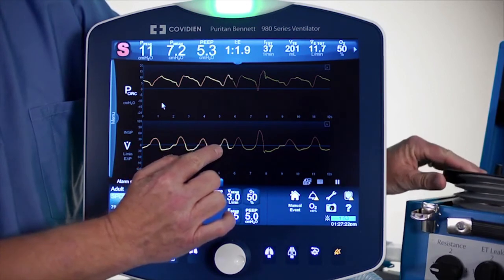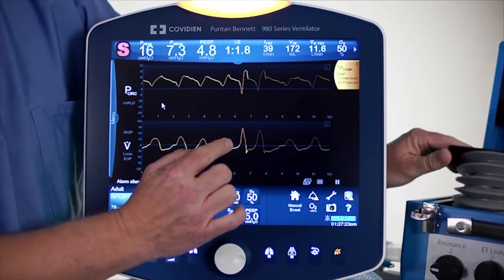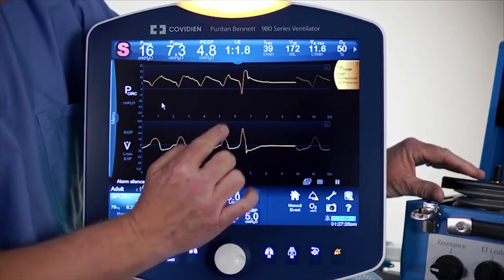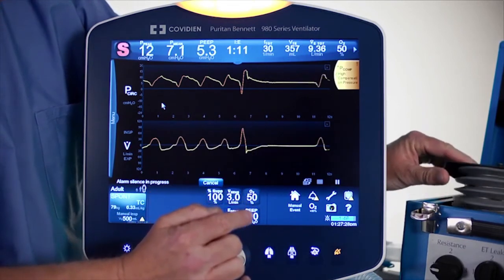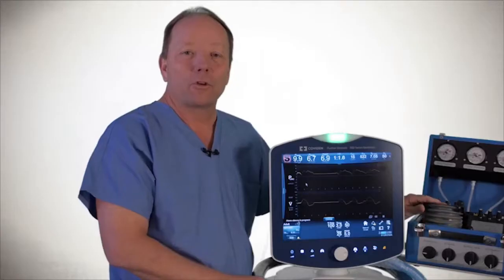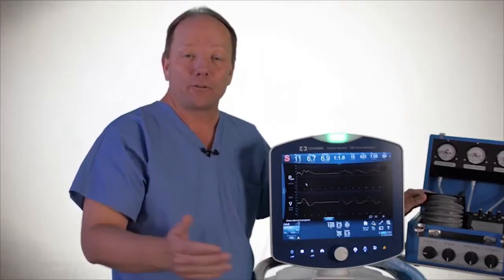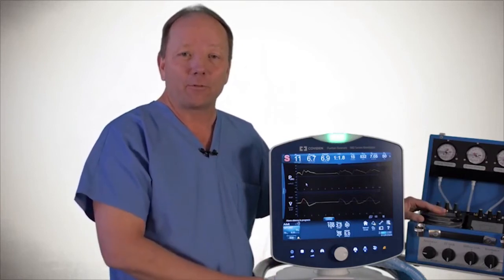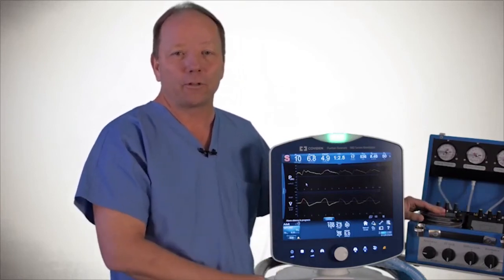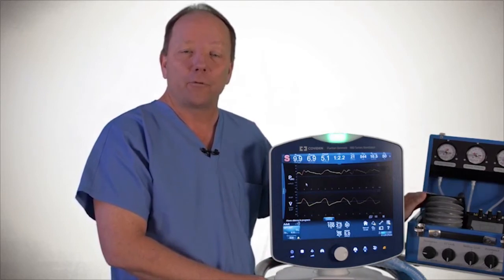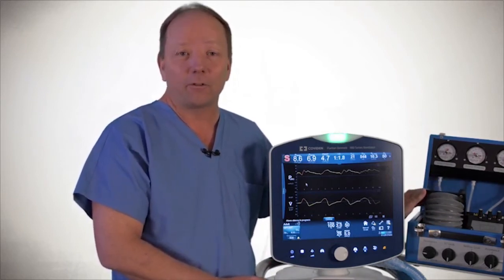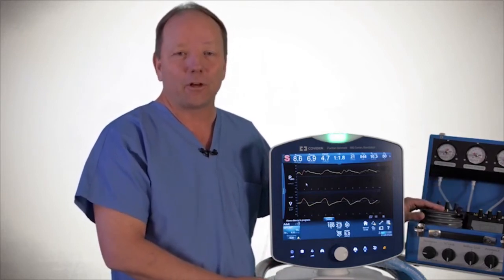It's using that lookup table: high flow means more pressure, low flow means less pressure. This software monitors the patient's inspiratory flow every 5 milliseconds and then adjusts the delivered pressure accordingly. With that, I would refer you to the operator's manual for additional details around the tube compensation software.